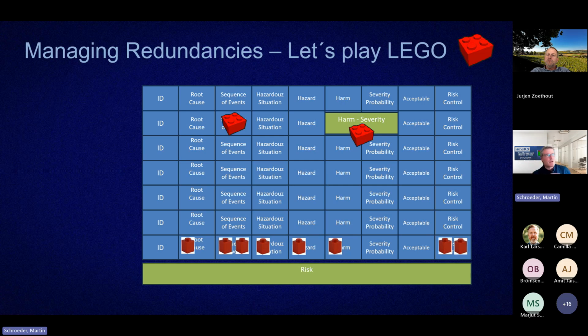Even though it's being reused in many different products and many different risk management files, it wouldn't make any sense to take one and the same harm that is severity class 2 in one file, and in the other file, severity class 4. What's the reason? If any auditor comes to a company and looks into risk management files and discovers these inconsistencies, you get some bad questions to answer. So we only want to define them once.